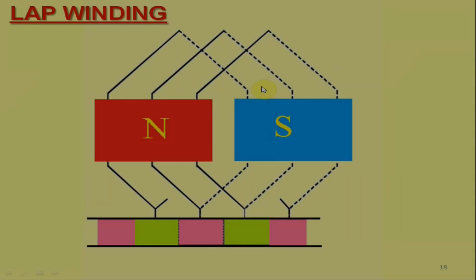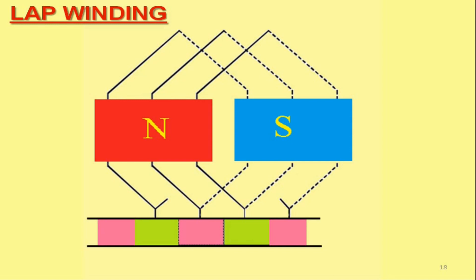This figure shows a simple lap winding where one can notice that the end of each coil is connected to the start of the adjacent coil, and the two ends of each coil are connected to the adjacent commutator segments. Moreover, in lap winding, the coil ends are bent inwards. Also, you may observe that each successive coil overlaps the preceding coil. Hence, the name of this winding is lap winding.